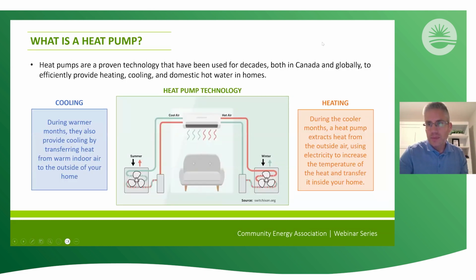So, what is a heat pump? This is really a proven technology. It's been used for decades, both in Canada and globally, to provide heating, cooling, and even domestic hot water in houses. The basic concept is that during the warmer months, it provides cooling by transferring heat from the warm air indoors to the outside of your house. So it's a heat transfer mechanism. During the cooler months, the heat pump extracts heat from the outside air, then uses electricity to increase the temperature of that heat and transfer it inside your home. The best performing heat pumps will take 1 unit of energy and turn it into 3 or more units of heat.